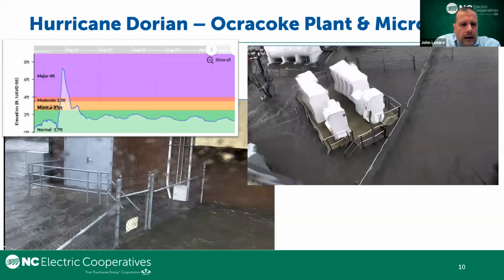The system went down, and I can tell you that once we got personnel on site, in the lower left-hand corner, you can see the water is at the door of the diesel generation site. And so we did have some prolonged outages where we had to get personnel on site to inspect the diesel, inspect the batteries, inspect the solar. But we were able to use the microgrid to restore power to the island a day earlier than the power from the mainland coming in was brought back. So definitely need to take environmental attributes into mind when you are planning your systems.